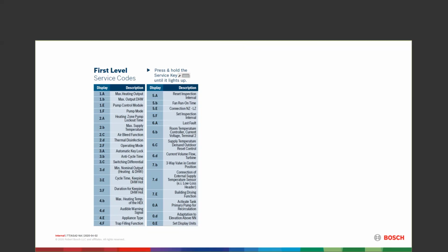A couple of the other ones: max heating temp of the heat exchanger, 4B, that's the plate heat exchanger. The duration for keeping your plate hot, that's 3F. There is an audible warning in there. You can shut that off. I prefer to leave it on. It beeps, it's kind of annoying, but it's a beep in the background that most people can hear. They'll call you if there's a problem, so that's why you leave that there.